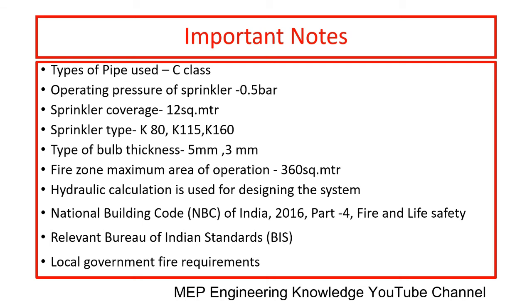Let us see some important notes. Type of the pipe used will be GI C class. The operating pressure of the sprinkler head will be 0.5 bar, the minimum pressure requirement. Next, sprinkler coverage will be 12 square meter. And the types of sprinklers are K80, K115 and K160. Type of bulb thickness will be 5 mm and 3 mm. Fire zone maximum area of operation will be 360 square meter. For this only we will use the fire curtain or water curtain.